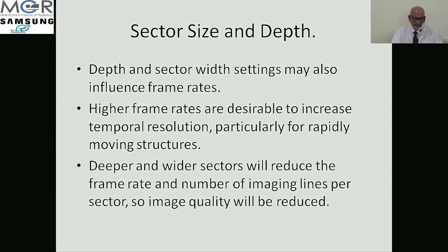Now, sector size, depth and sector width settings may also influence the frame rate. As I told you, the basic difference between USG and echo is the frame rate. Because we are studying a dynamic organ, we are more interested in frame rate. If you have a better frame rate, then you can have better visualization of the motion of the various structures of the heart. So higher frame rates are desirable to increase the temporal resolution. Temporal resolution means the movement in relation to time, particularly for rapidly moving structures like the valves and endocardium.